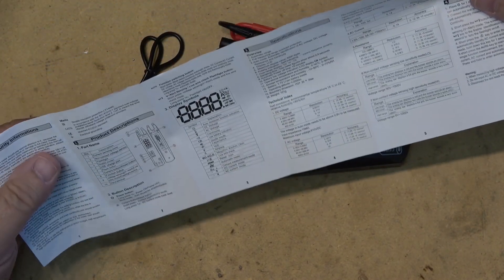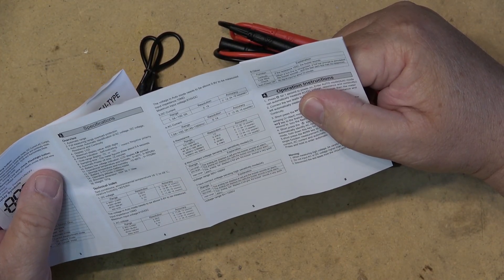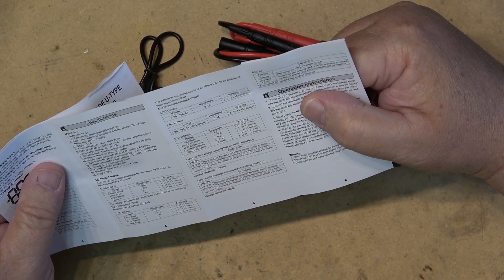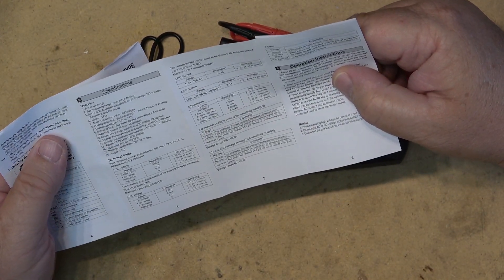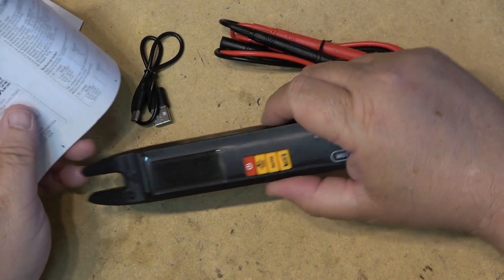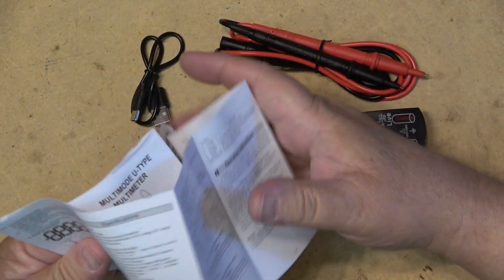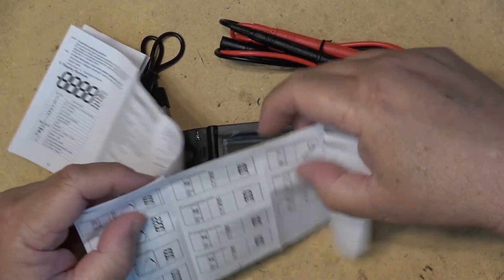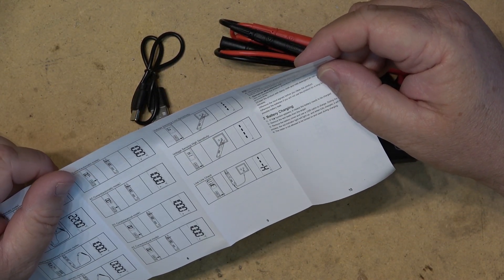It features a rechargeable battery — there should be some charge in it. It has a range of up to 40 megaohms on resistance, 100 amps on AC current and DC current. It has a range up to 610 volts DC and 610 volts AC, but the maximum input says 600 volts. Auto input — get your common and your input lead. It has non-contact measurement as well — non-contact voltage detection.